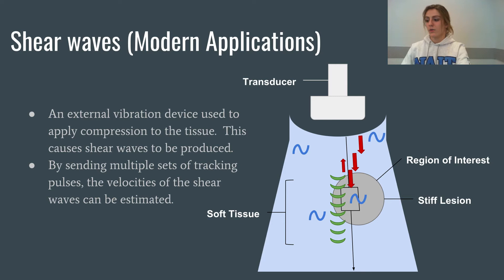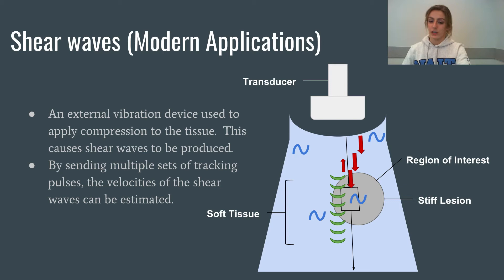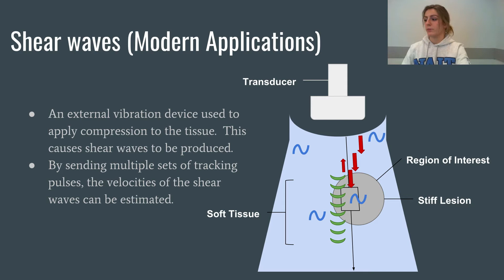When we use shear elastography today, we use an external vibration device and shear waves to apply compression to the tissue, which causes shear waves to be produced. Shear waves travel perpendicular to the compressional wave and are much slower than the compressional waves — this is what makes it possible to track them. To track them, we look for small displacements of the tissue in the lateral dimension. The push pulses, or compressional waves in green, create the shear waves shown in blue. These travel perpendicular to the push pulse. The transducer then sends out tracking pulses — the red arrows — which measure the tissue displacement caused by the shear waves. By sending multiple sets of tracking pulses, the velocities of the shear waves can then be estimated.